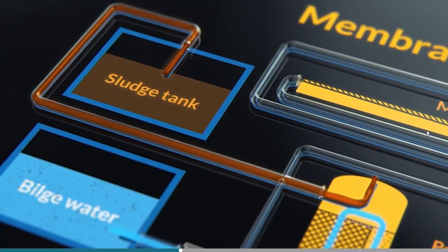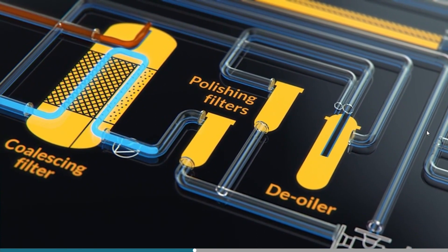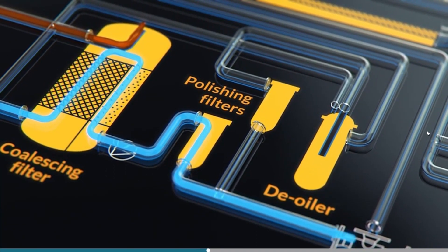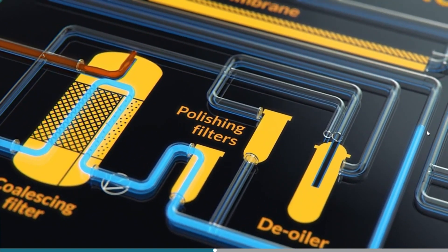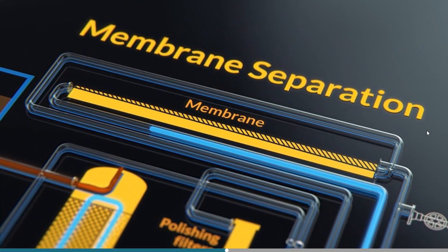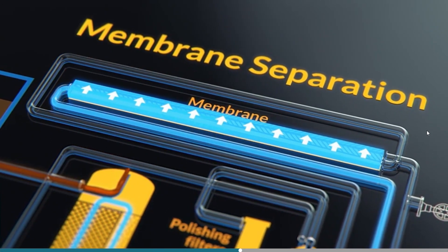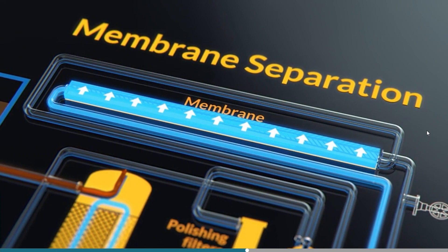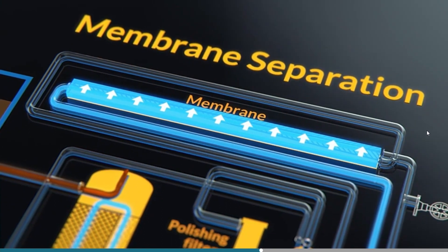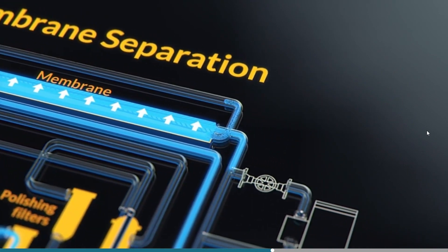The second stage typically consists of one or more further stages of filtration, often referred to as polishing filters. These stages are also usually based on gravity and coalescing, but also include membranes that will not allow the passage of oil droplets, so that purities of 5 ppm are claimed by the manufacturers. A process or booster pump forces the water through a filter membrane, which removes any remaining emulsified oils and contaminants. Inside the membrane chamber, the water is split into two parts: clean water and rejected water.